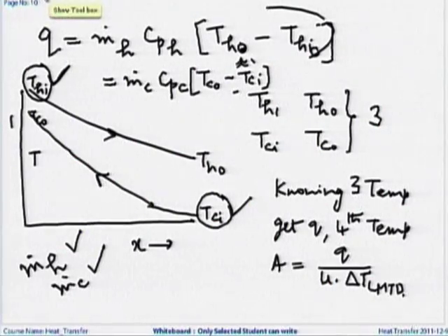If you are talking of a classroom type of problem, you can use this kind of solution, where you have everything known, inlet and exit temperatures are known, you can do this closed form solution like this. But in real life, in application, or in a design environment where you want to calculate the length accurately, where you will want to take the property variation, etcetera, what is typically done is you split and march in every incremental length. So, you choose a particular length dx.